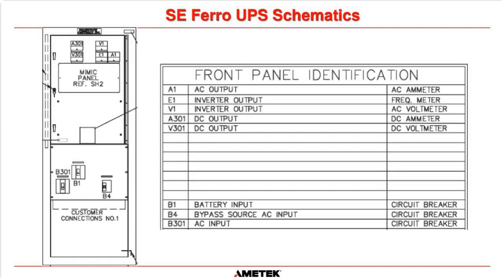Okay. And then on the left here, you can see the labels on this particular UPS. And remember, all of our UPSs are customized. So each UPS will have different meters. But let's take this one, for example, V301. If we look over here at the table, V301, that is the DC output voltmeter. Okay. And A1, if we look up here, A1 is measuring the AC output, and it's an AC ammeter. Okay, so that gives you a description of what the meters are. And then you can see in this section here, our breakers are labeled. So B301, that's this one here, that is the AC input, and it is a circuit breaker. So quite self-explanatory.